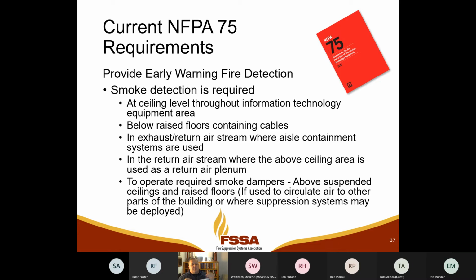And then finally, we need to have smoke detection located to operate required smoke dampers above the suspended ceilings and below the raised floors if that air is being used to circulate air, or those dampers are being used to circulate air to other parts of the building, or where suppression systems may be deployed. So basically, we've got to have smoke detectors so that we can operate dampers if it's part of the whole sequence, okay? Whether it's limiting smoke spread out of the data center or into the data center, or shutting down dampers so that the suppression system works.